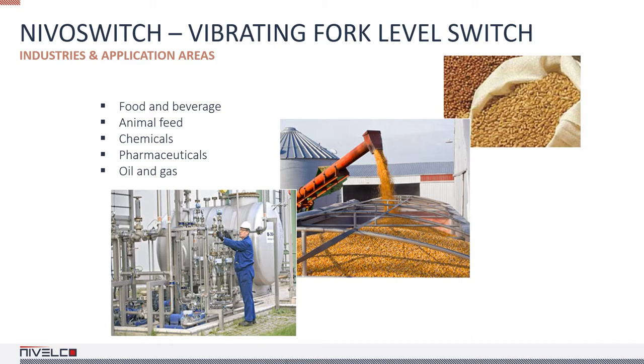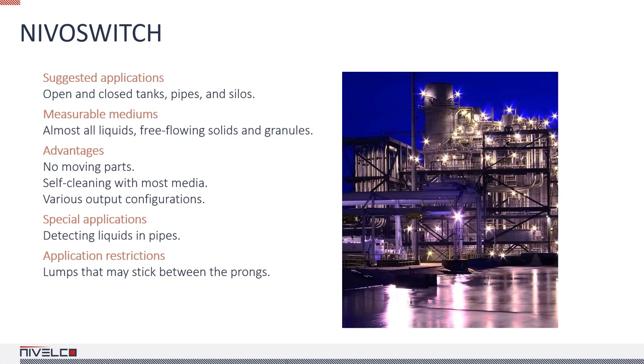Units with parallel vibrating prongs are ideal for liquids, and units with diverging vibrating prongs are designed to measure solids. The plastic coated version is recommended for aggressive mediums, and the highly polished version is for use with abrasive materials. Nivoswitch vibrating fork level switches control the filling and emptying of pipes, silos, tanks, and hoppers, and can also send failsafe alarm signals to prevent overfilling and dry running. One of the advantages of vibrating forks is that they are self-cleaning under certain circumstances. However, mediums that may stick between or onto the prongs should be avoided.